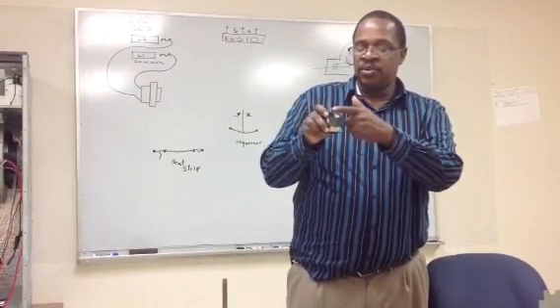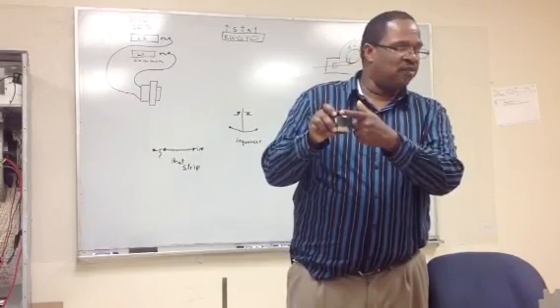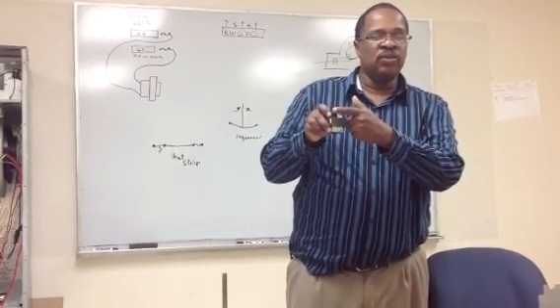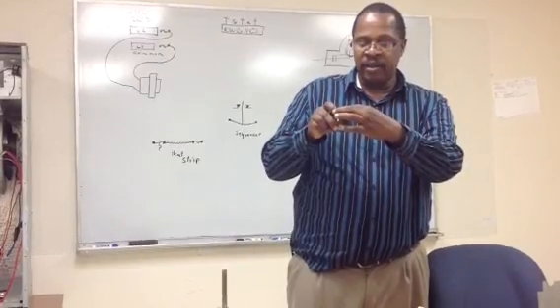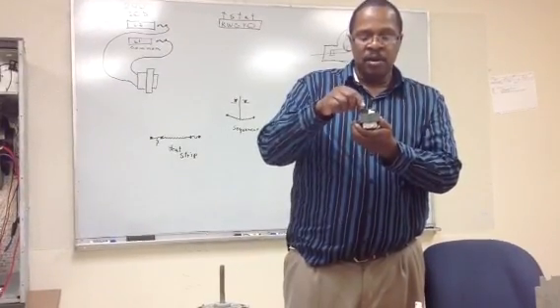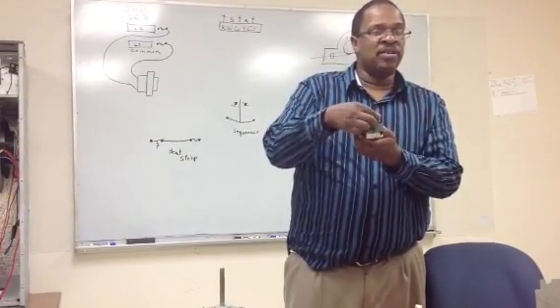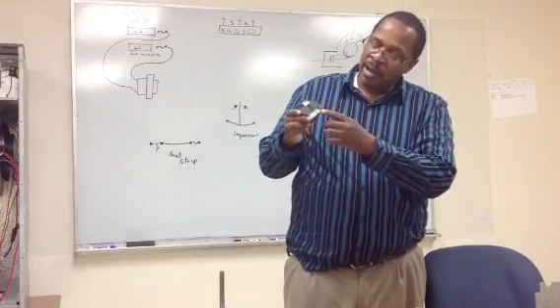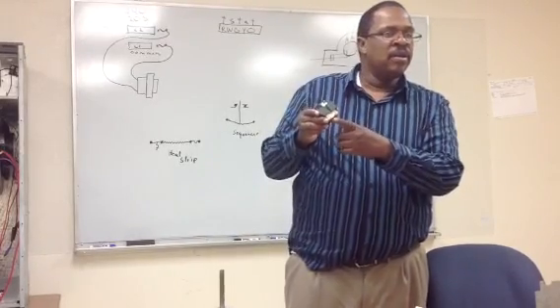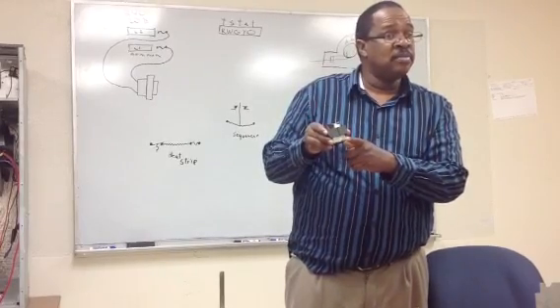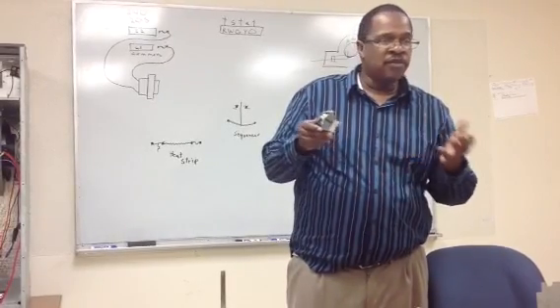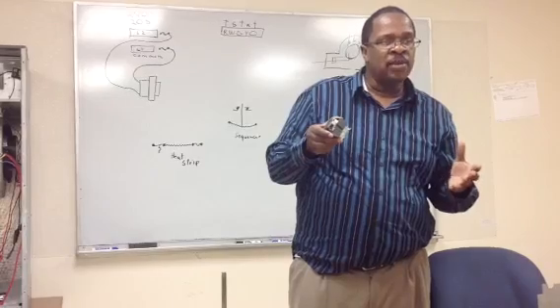The two taps, if you read the side of the transformer, is usually your 24 volts. Some will have wires coming off that you hook up to. Some will have male connectors that you will plug a female connector over. On the bottom, we have a common, we have our 208 tap, and we have our 240 tap.